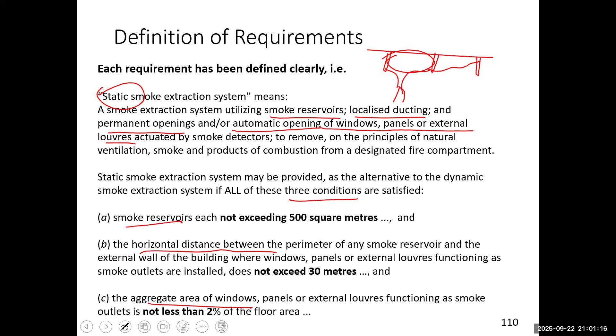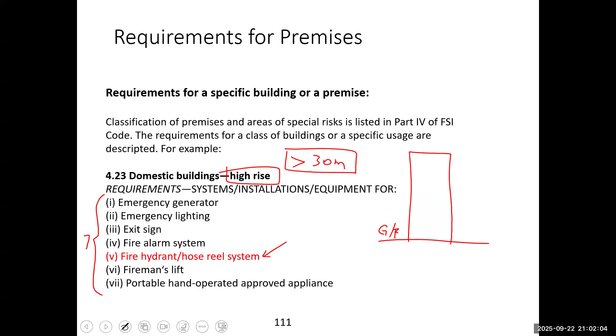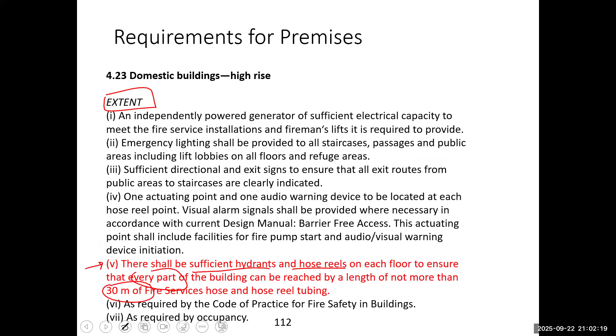Required for premises for the domestic building, high rise. We have several requirements. Okay, high rise refers to a building of height greater than 30 meters, or where the evacuation route from the top to the ground floor is 30 meters. So hydrant and hosereel is one of the requirements. Okay, the extent of requirement further, we have 7 items here. The 5th item, we read through the 5th item. Sufficient hydrant and hosereel to be provided on every floor. Make sure that the 30-meter hose is covering every part of the building.